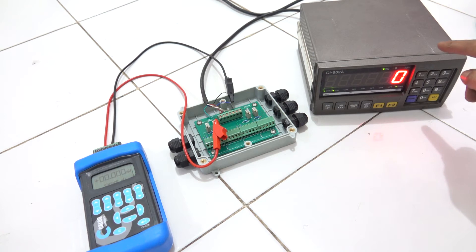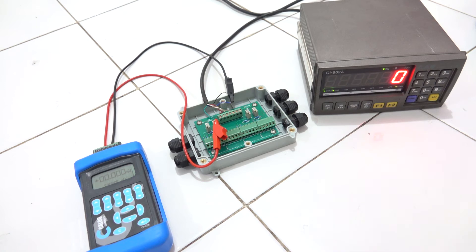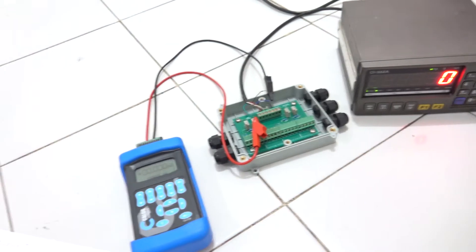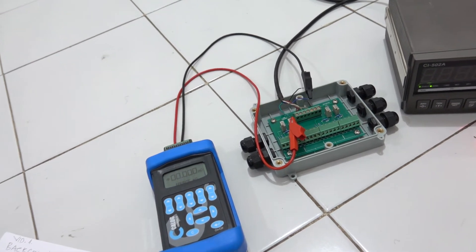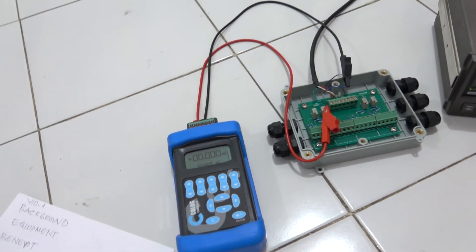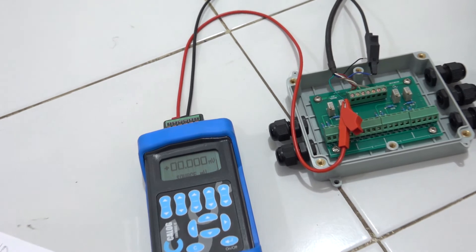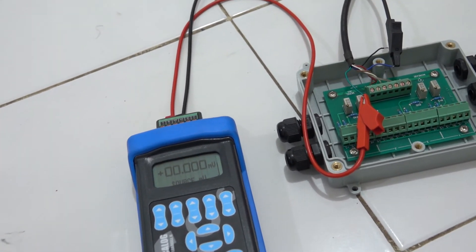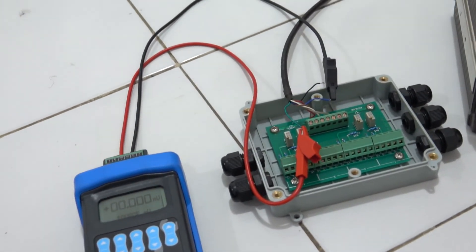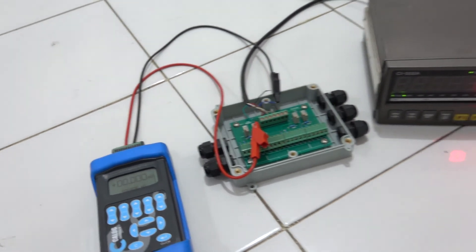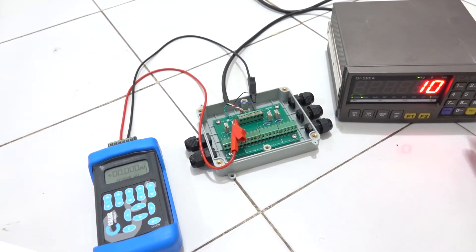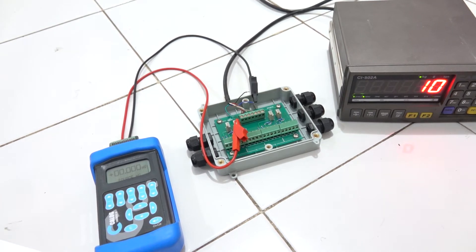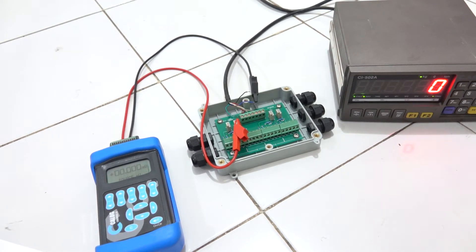Or load cell display, they call it sometimes. As you can see here, now is zero volt. You can see zero volt here generated by this Calc. And as you can see, at zero volts, the display indicates zero. In this example, it's zero kg.